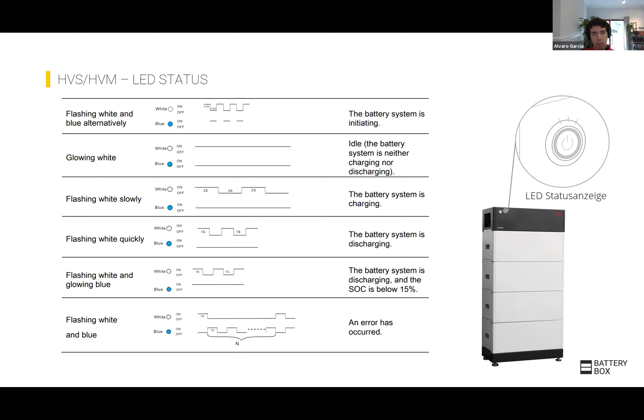Once it has been commissioned, or well, even if it has not been commissioned, you will notice in the top left-hand side an LED. There's a place where you press the button to switch on, switch off the system. This LED will give you some indications: confirm if the battery is working normally, if the battery is waiting for the inverter, if there's a low state of charge. That's a lot of information that the LED will provide you. And this is explained in the manuals, what each of the signals mean. And if there is an error, there are 16 different codes that will tell you exactly where the error is. If you have a doubt, you can also use the BConnect Plus, which is on the EFT Systems website, to get the read of any errors.